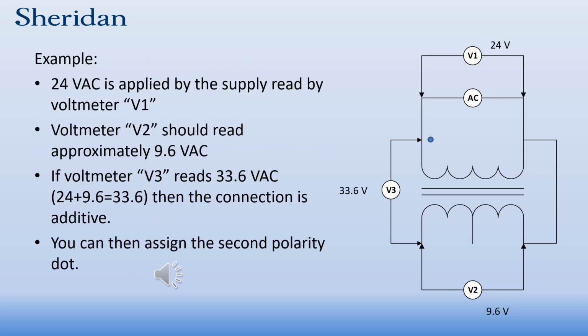Okay, let's look at it as an example. We should be testing, of course, from the high voltage side, which we can tell by our ohmic reading, higher ohmic reading for higher voltage. What we would do is apply a 24 volt voltage to the primary side, read by voltmeter V1. Voltmeter V2 should read 9.6 volts, or somewhere close to that because of the transformer ratio.